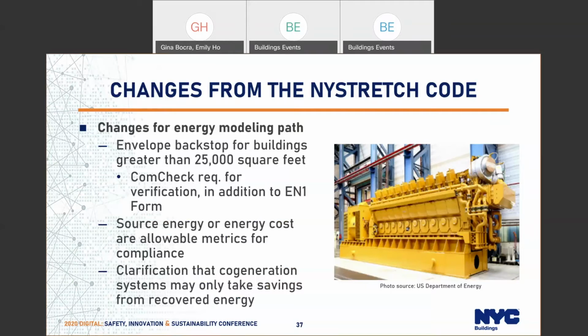The first is what we colloquially call the envelope backstop. So there is now an envelope backstop requirement for buildings greater than 25,000 square feet. In the past, there was no minimum requirement on insulation in walls. If you followed energy modeling, you could trade off all the insulation in the walls for higher efficiency lighting or HVAC. You can still do that. However, there is now a threshold that you cannot cross. And the way you demonstrate compliance with this is there is a COMcheck that I'll show you in later slides. I'll give you a visual of what it looks like.